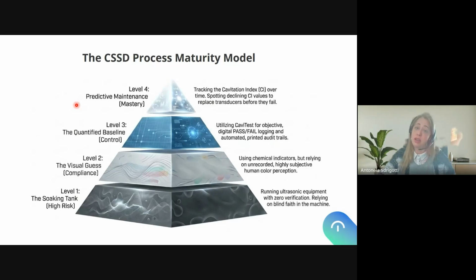So if we continuously monitor on a daily routine basis how my machine is working, mapping our tank with indicators, changing positions, we make sure not only that today my machine is working, but that it is not reducing the energy or the effectiveness that it should deliver to my instruments. So just by measuring the cavitation index, we can monitor over time how my machine is working. And if we see a reduction in the cavitation index in specific positions, we can take preventive actions to avoid major maintenance because some transducer breaks down, okay?